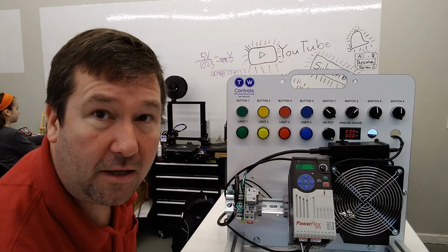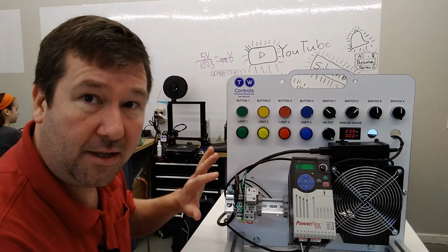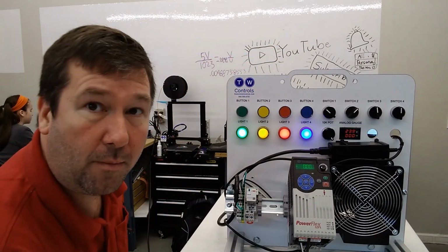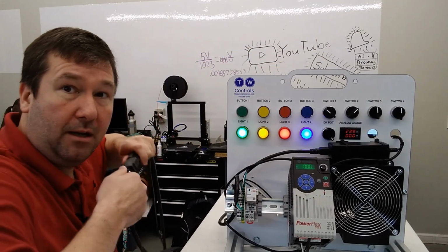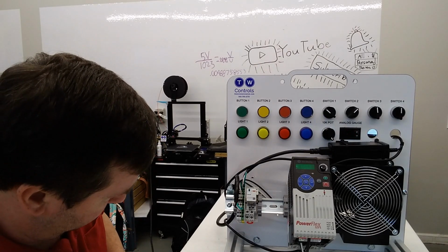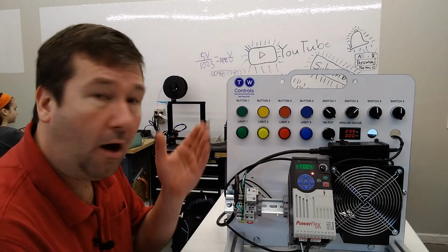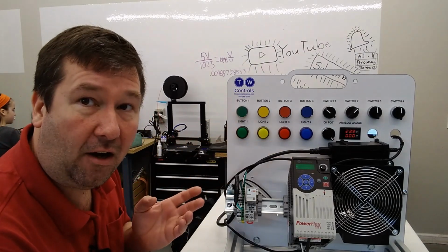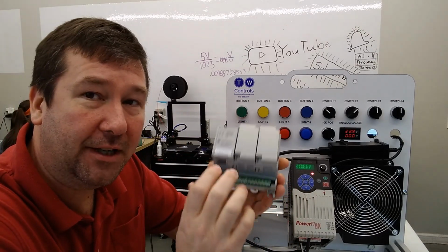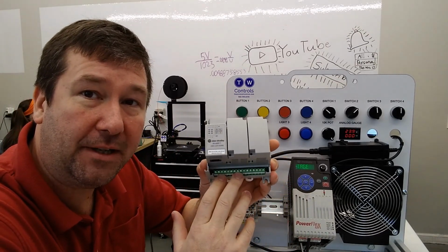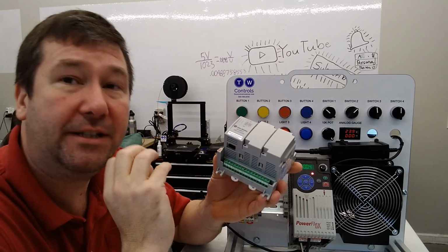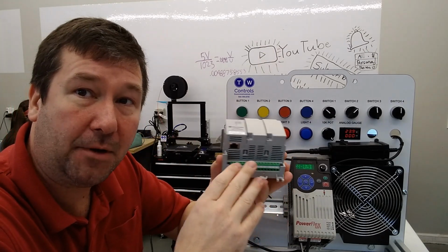But by default, if you programmed yours just like I showed you in the exercise, and we start our four motors, and then we unplug the power, when we plug it back in, all four lights will stay off. And that is because all of the outputs on a Micro820 PLC are non-retentive. In other words, they reset on power up no matter what.